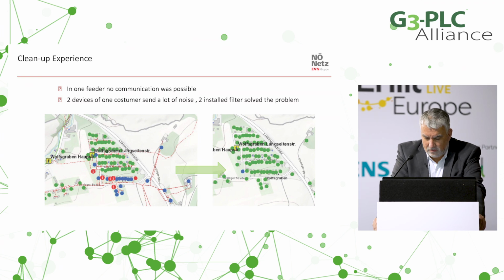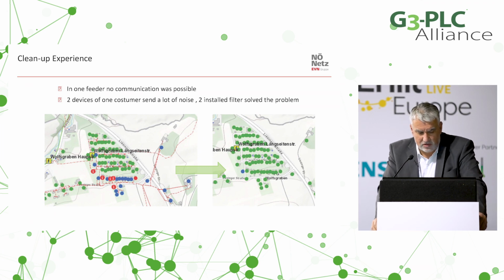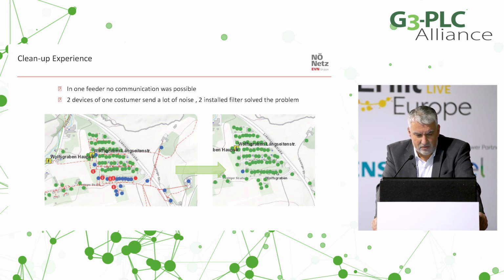Only to show you an example of our cleanup experience: in one feeder there was no communication possible. We monitor all this with our GIS system. You see this on the blue point. There was one meter, one customer, who had two devices which sent a lot of noise. After we installed the filter, you see it on the right side, everything is green. The blue one, there was a fault on the meter. But we go into the field, we measure the noise, and then sometimes we go into the household to find the device which sends us the noise.